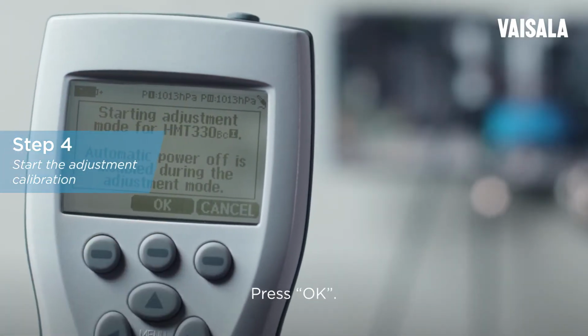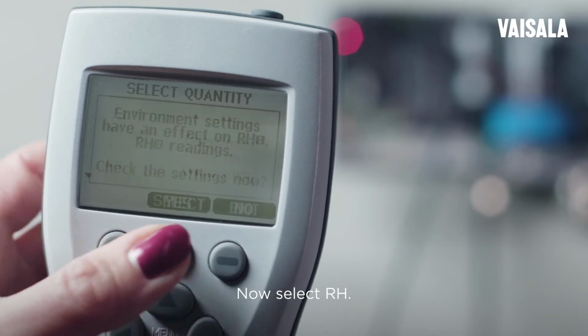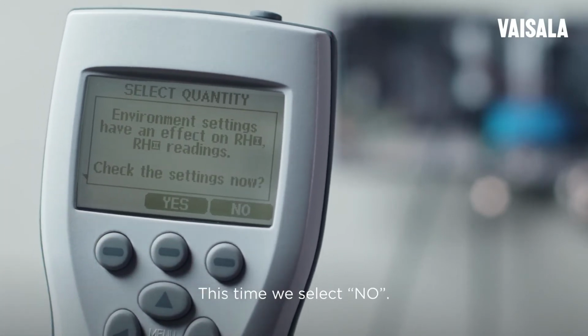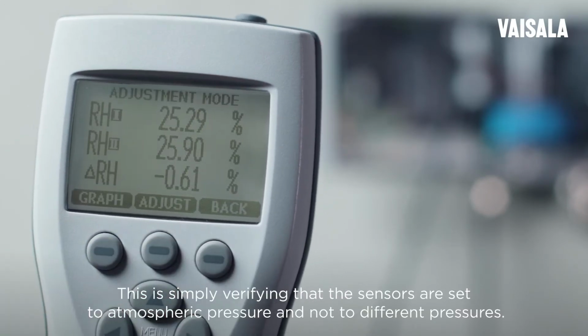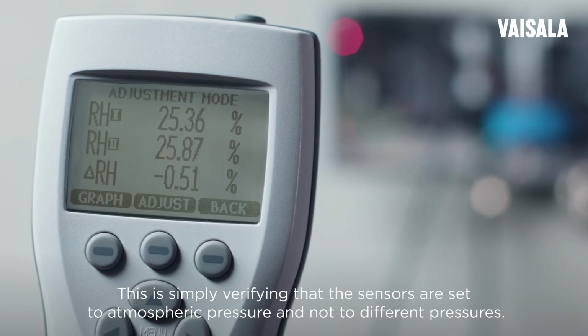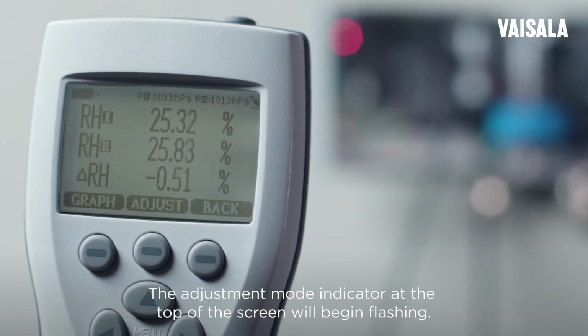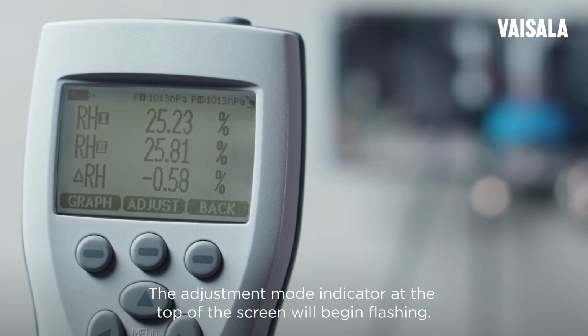Press OK. Now select RH. This time we select No. This is simply verifying that the sensors are set to atmospheric pressure and not to different pressures. The adjustment mode indicator at the top of the screen will begin flashing.